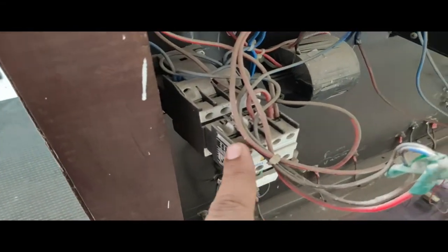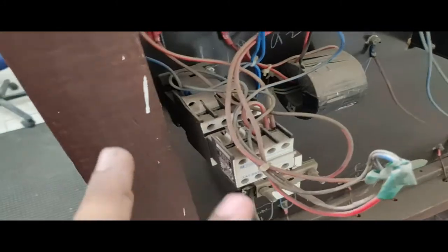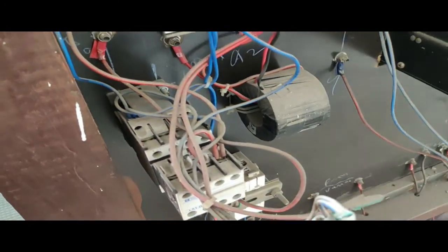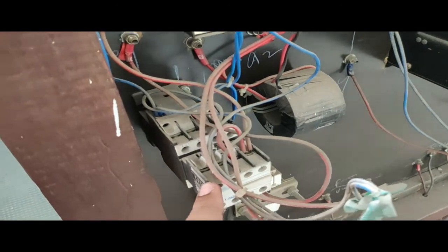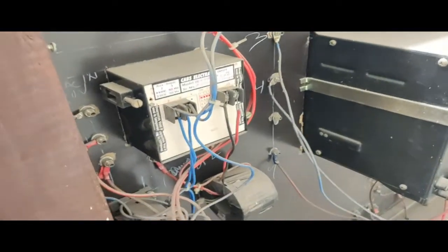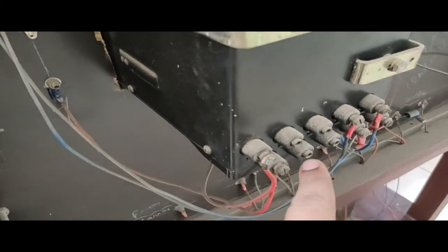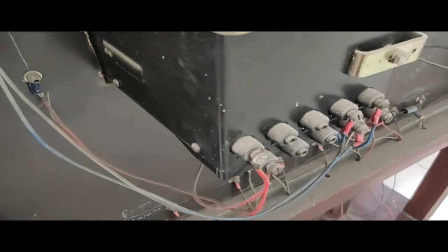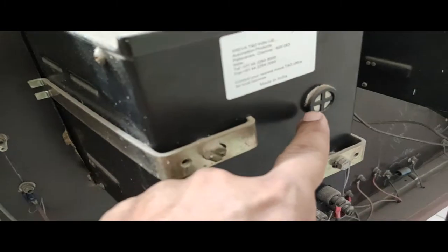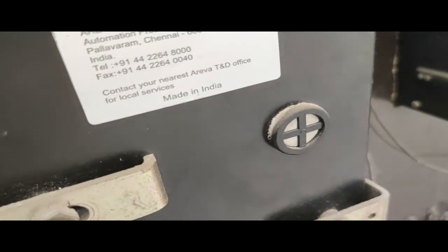This is one contactor. As I mentioned, a relay is a very low power device which is not able to switch on or switch off any load here. So the relay controls this contactor, and this contactor can handle the actual loads. In substations, the relay will definitely control a circuit breaker. But as the power requirement here is low, a circuit breaker is not installed here, rather one air contactor is there. That one is the MCB, and this is the back panel of the relay. Here the terminals are there. Some terminals are not required here, that's why some are left blank, and some terminals are required according to the circuit diagram. This is the casing of the relay, and this is the breather. One filter is also there, so that dust from the external atmosphere does not go inside. That's why the breather is there.